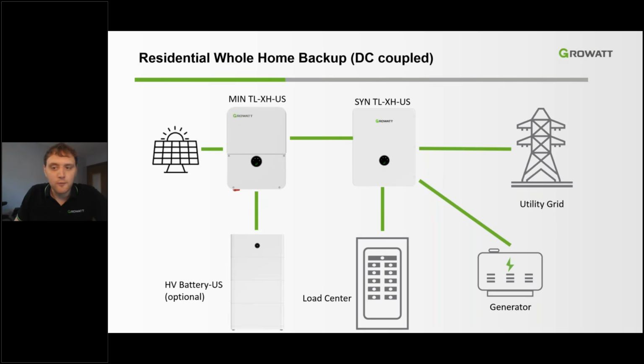The battery is not required to achieve the whole home backup, and the customer's loads can be powered directly from solar during the outage. In the future, Growatt plans to allow up to 3 inverters access with the SYN device, and even allow for EV charging during the event of backup. But these features are not quite implemented as of yet, so look out for this in the future. We plan to have up to 3 inverters accessing the SYN device at one single time, generating even more backup capabilities for your customers' loads.